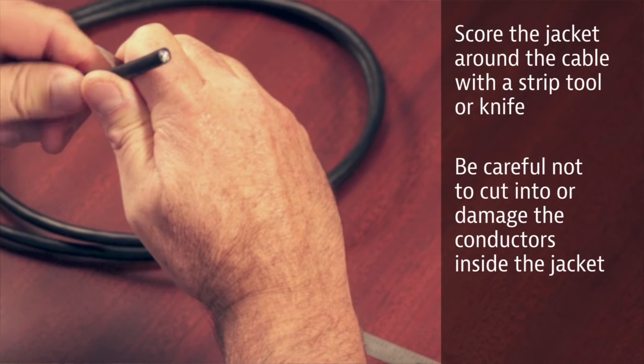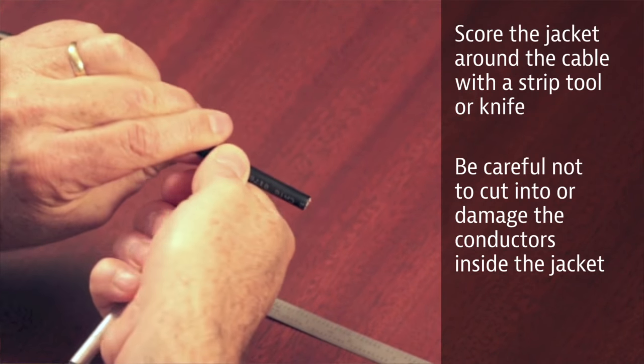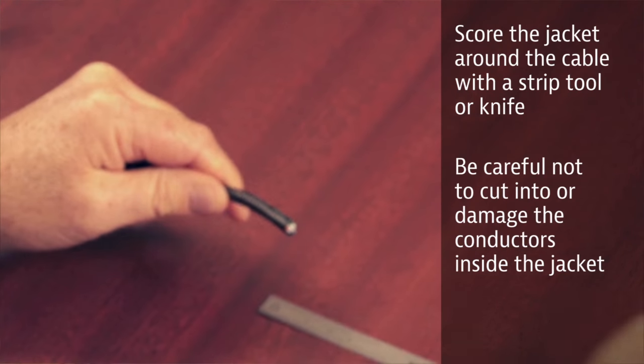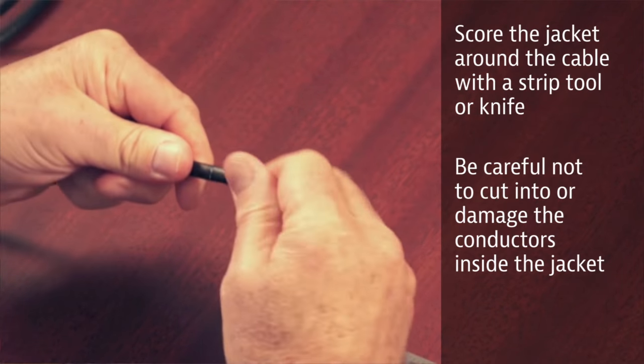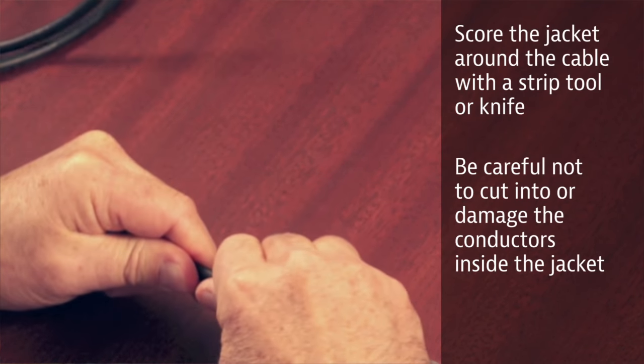You can use a strip tool like the cigar cutter or you can use a hobby knife like the Xacto knife. You can use a box knife, but you want to score the jacket around the cable. Do it carefully - you don't want to go too deep or cut your conductors. If you flex the jacket, you'll see the jacket breaks apart and you can pull this off.